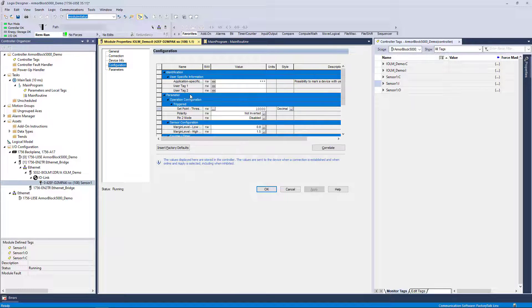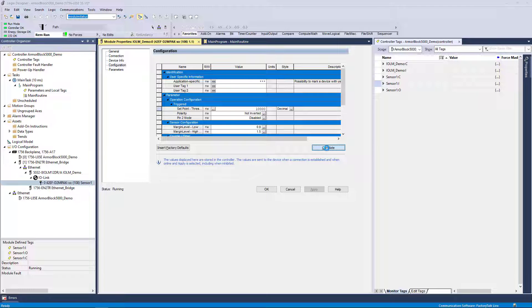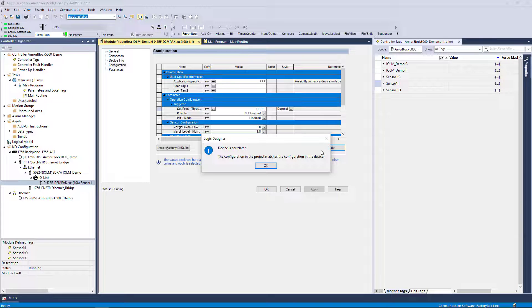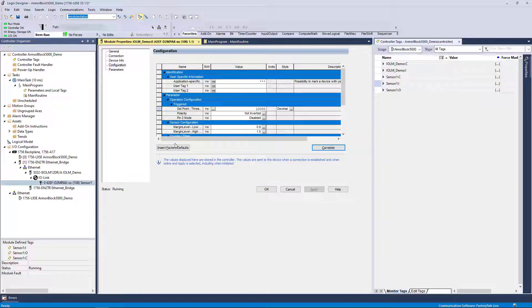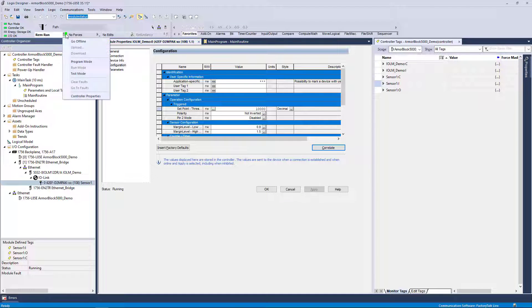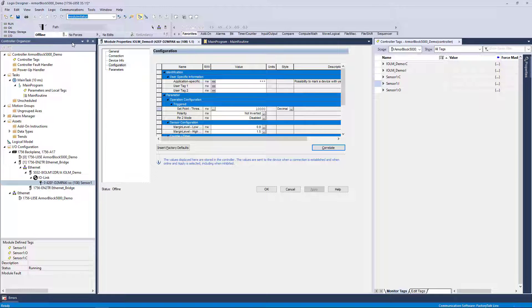Back on the Configuration tab, we can attempt a correlation, but we will be notified that there are no differences to correlate, since the change has already been loaded in the IO-Link device through this workflow. The next workflow in ADC mode will demonstrate what happens when a configuration change is downloaded to the processor.